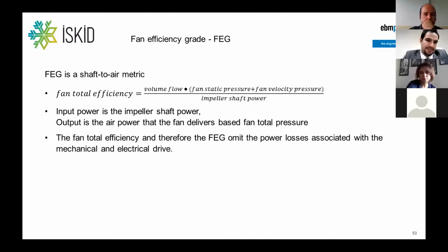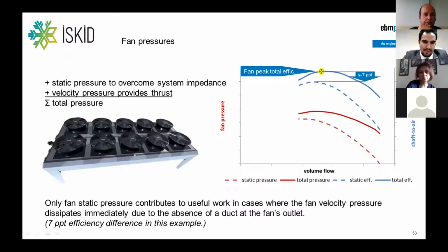And how to calculate this is fan total efficiency. As mentioned before, it's the flow multiplied by the total pressure, divided by the shaft power. So fan total efficiency is used, and therefore FEG omits the power losses associated with the mechanical and electrical drive. Static pressure and total pressure I explained before. It's one thing that has to be considered when comparing the systems: do we look at static efficiency or total efficiency? At the end, it doesn't really matter, because fan manufacturers don't sell efficiencies. I think they sell the input power at a job that has to be done, and so the best way is to look at the power consumption.